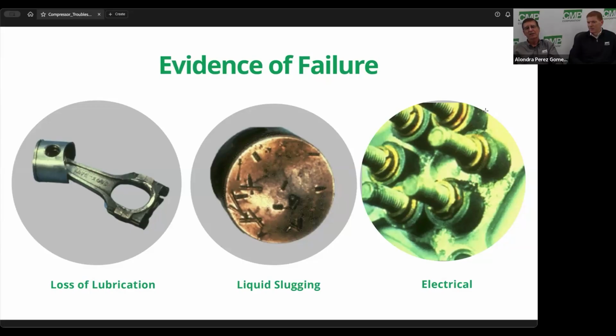So sooner or later, it'll heat that post up and then the terminal starts leaking. Always make your electrical connections metal to metal. You want a nut on the bottom, and then you want your wire, and then you want a nut on top to make sure it's all metal to metal on your electrical connections.